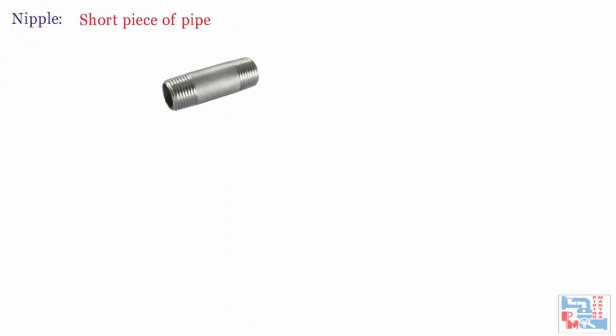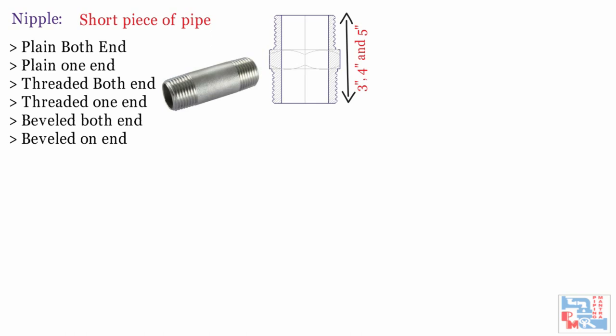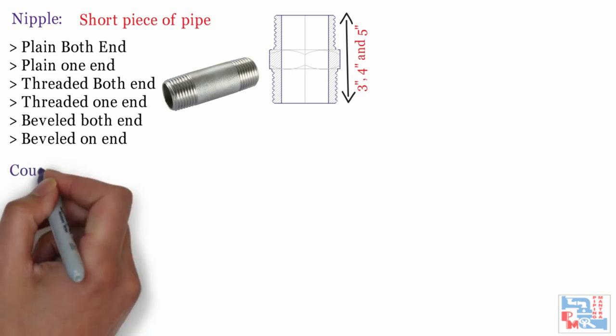A nipple is a short piece of pipe usually defined with different end connections, like plain both-end, plain one-end, threaded both-end, threaded one-end, beveled both-end, beveled one-end, and combinations such as one-end plain and one-end threaded. The length of the nipple is usually specified by the overall length including threads. It is usually available in 3-inch, 4-inch, and 5-inch sizes.